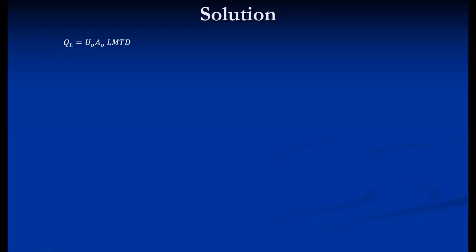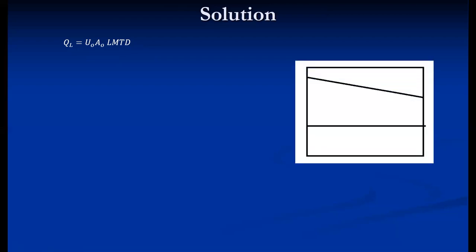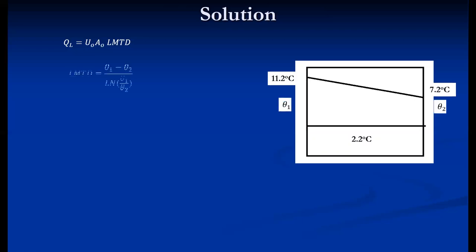Since U values — H_i and H_o — are indirectly given, we use the LMTD approach. The equation is Q_L = U_o · A_o · LMTD, where U_o uses the outer area. The evaporating temperature is 2.2°C, water inlet is 11.2°C, water outlet is 7.2°C. So θ1 and θ2 are calculated, and LMTD = (θ1 − θ2) / ln(θ1/θ2). The Q_L value is also known from the 20 TR rating.